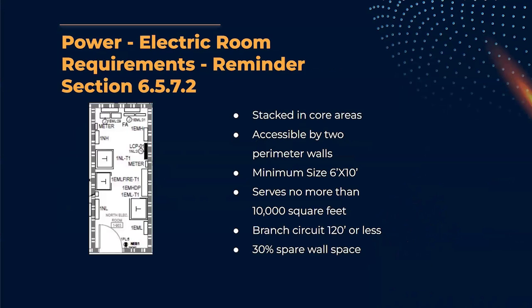We cannot distribute out to our loads if we're surrounded by non-penetrable walls. 6 by 10 is the minimum size for an electric room. You can make them larger. They serve no more than 10,000 square feet. That's unique to GSA. The intent there is to limit voltage drop situations and also to not disturb.